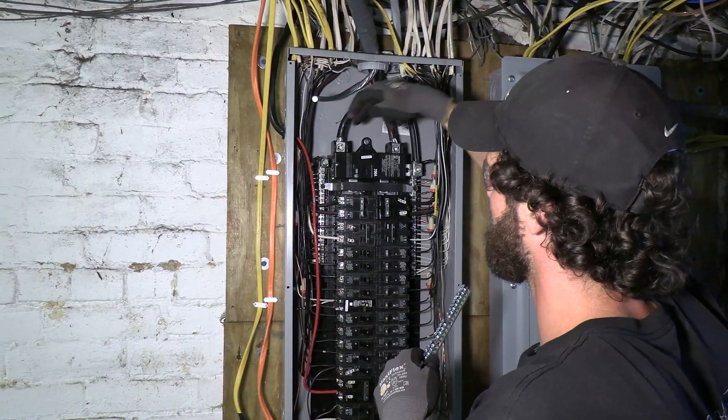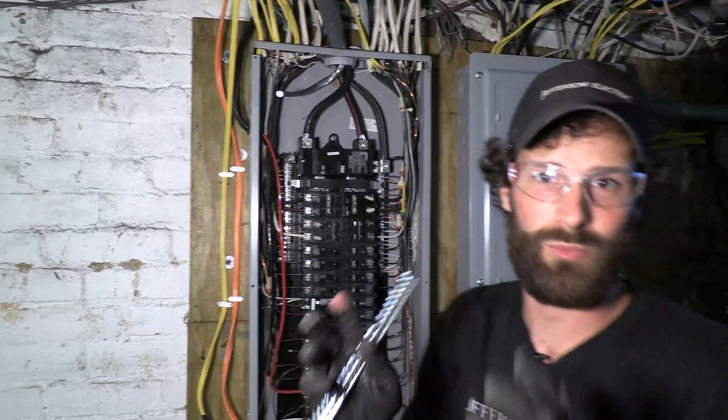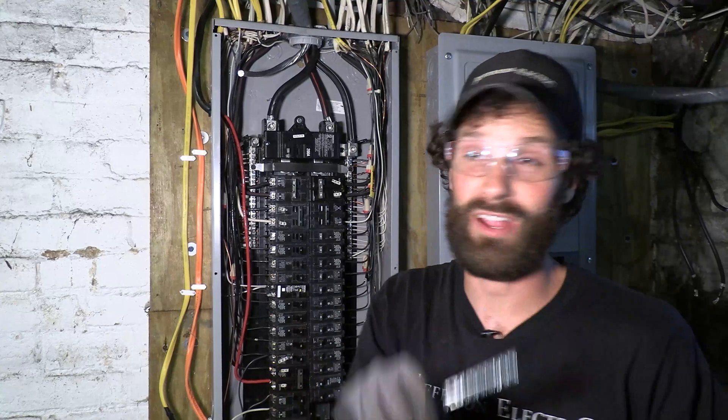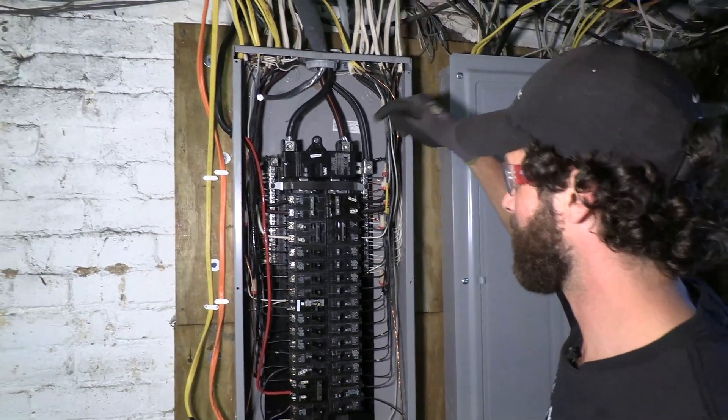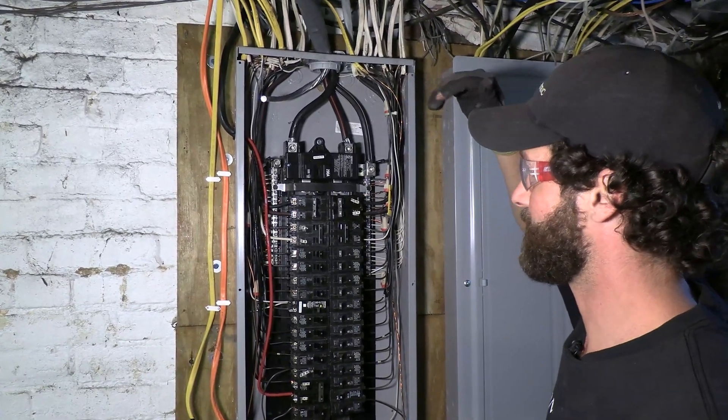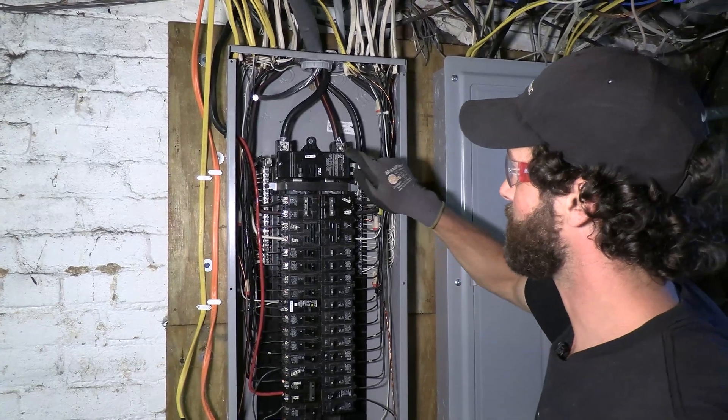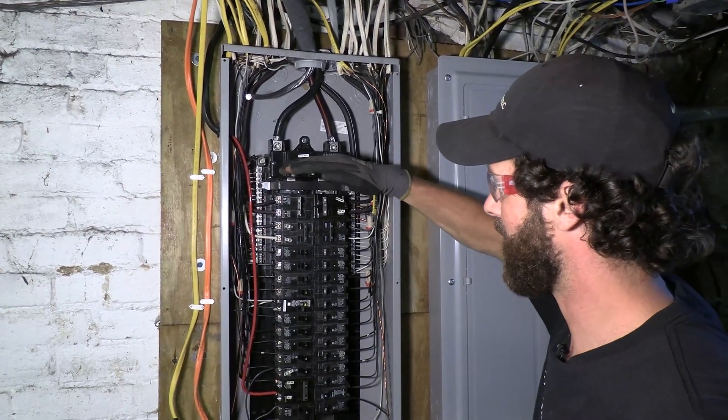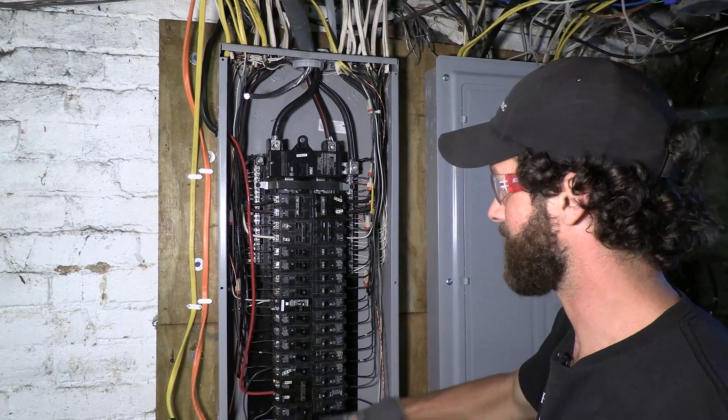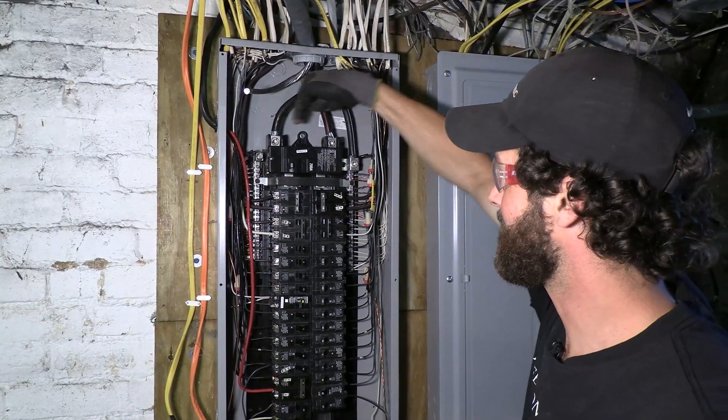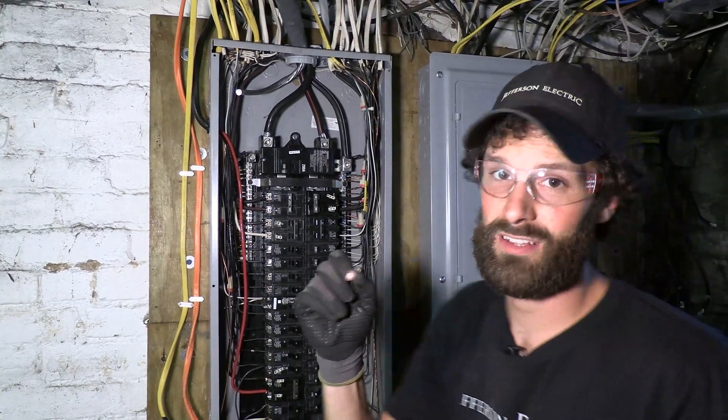Those terminals are still live. So a quick bit about safety. One, you need to know the codes and standards in your area. Two, you need to have test equipment so you can confirm that things are de-energized. Three, when you de-energize the main panel, everything here down is de-energized. But you have to understand these live terminals are still energized.